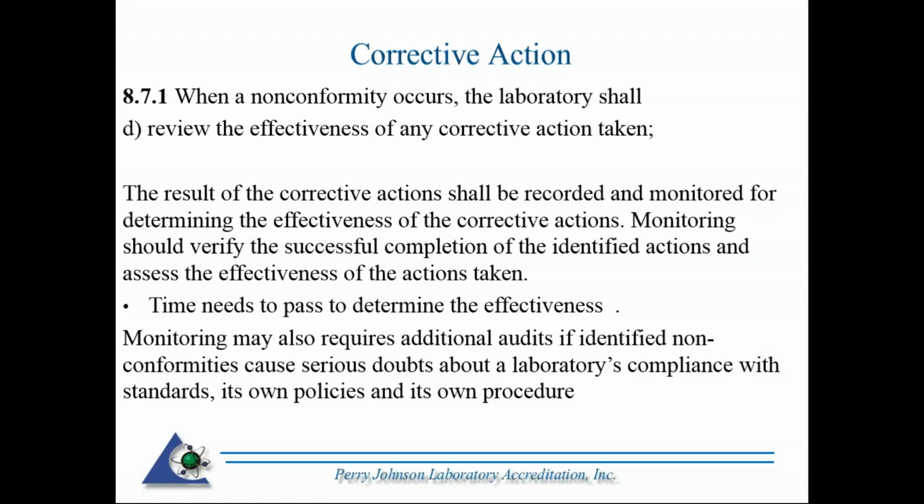In other words, and what I like to tell folks, I've reviewed many corrective action reports, and I see all the requirements captured, including a sign-off and the determination of the effectiveness of the corrective action. I've seen them sign off on the same day that the corrective action was implemented. You really don't have a feel for whether or not it's going to be effective unless you have some time passed.